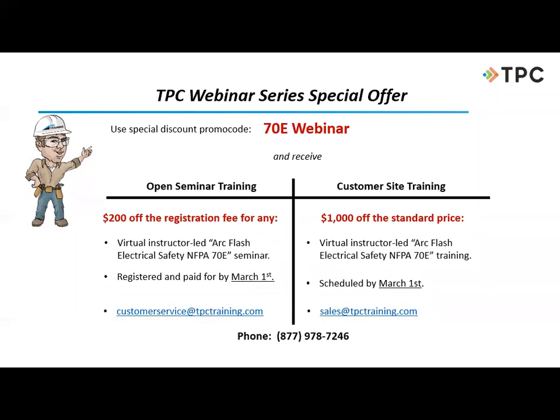Now, so long in the history of NFPA 70E did we get tied up with the PPE category method, which does have upper parameters. The upper parameter there is 40 cal. So that's it. If you're using method number 2 to choose your personal protective equipment, you are done at 40 calories. And the standard says this: you would now have to switch over to the incident energy analysis method. And of course, the incident energy analysis method is where we're going to be using some software, come into your facility, model your electrical distribution system, and come up with the fault current and clearing time throughout the whole plant, and put a label on that says what the incident energy is at a particular piece of equipment.